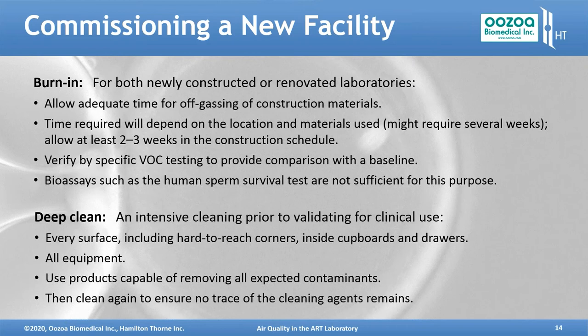After the burn-in, you do a deep clean. This is an intensive cleaning prior to validating for clinical use. Every surface, including all the hard-to-reach corners, inside the cupboards and drawers, and underneath these things as well, must be cleaned. All the equipment's cleaned, inside and out. Use products that are capable of removing all expected contaminants. Then you clean again to make sure that the cleaning agents themselves have been removed.